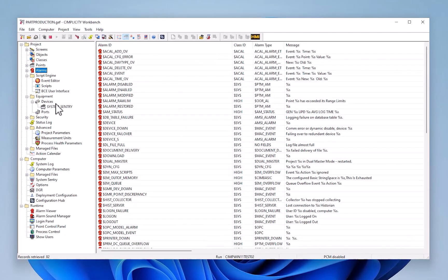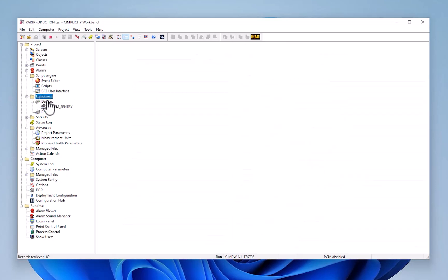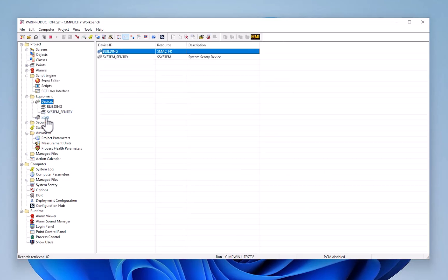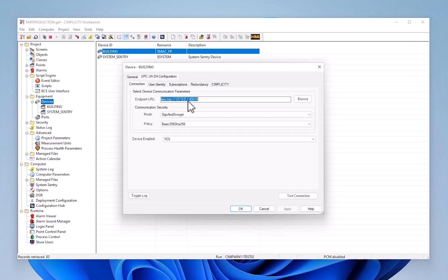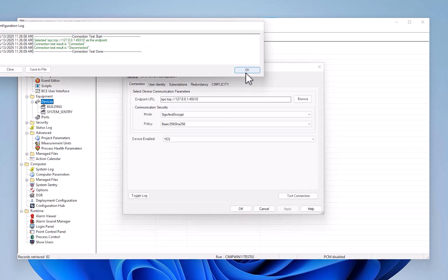To configure equipment in CIMPLICITY, you go to the equipment tab and set up a number of devices and ports. Ports are the actual process that makes the communication path, and you can have one or more devices for the different types of devices you want to communicate with using a certain protocol. For example, I have a device here that is an OPC UA device that lets me connect to an OPC UA server and retrieve data from it.